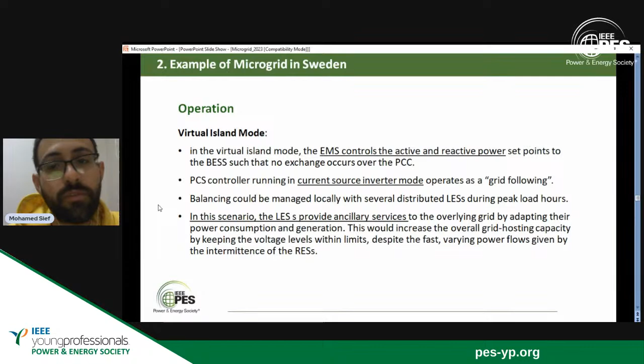Okay, in this case, the power system controller PCS inverter is running in voltage source inverter mode. Voltage source inverter mode means it will have constant voltage in this case. And it operates as grid forming because, as we mentioned before, it will set the value of the voltage and the value of the frequency, which will be working during the islanding mode. It allows the BESS to seamlessly transition between the grid connected mode and the islanded mode.